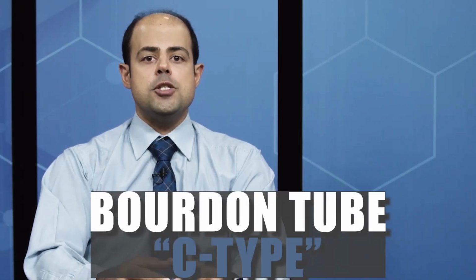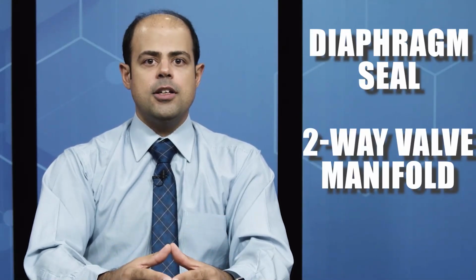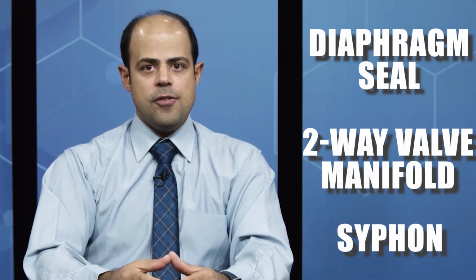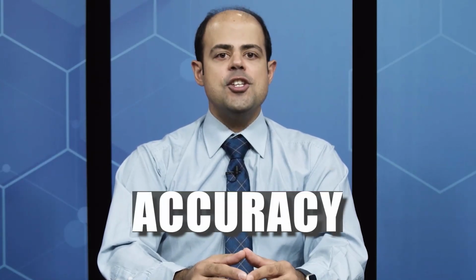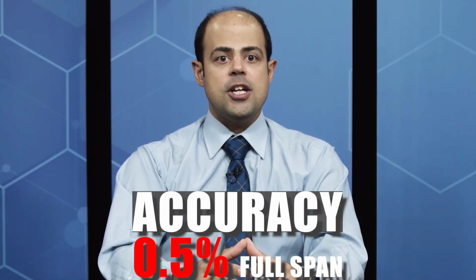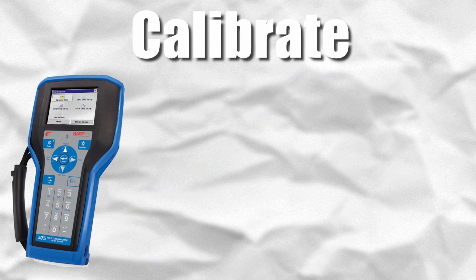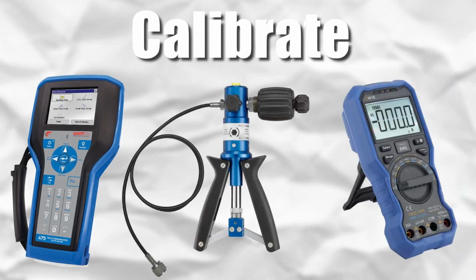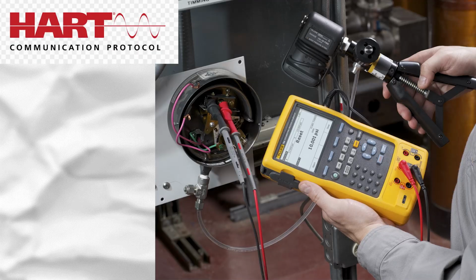When it comes to pressure, the most famous measuring element for a gauge is the Bourdon tube, particularly the C-type. There are many accessories for a gauge, such as a diaphragm seal, a two-way valve manifold, and a siphon used in hot steam services. For designing and selecting a pressure transmitter, you need to bear in mind that accuracy is a vital factor, and it's usually considered better than 0.5% of full span. To calibrate a pressure transmitter, you would apply a HART communicator, a hand pump, and a multimeter. To clarify, HART is a typical protocol applied to communicate with an instrument.